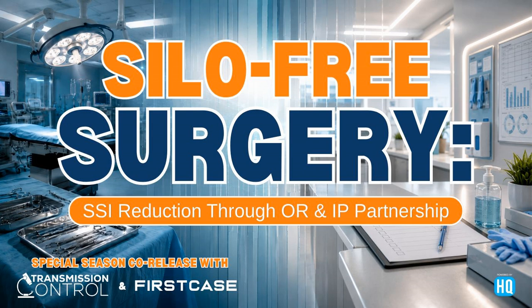Right. Yeah. Or somebody uses the instrument incorrectly in the OR and there's damage or a chip or something. Yes. But I think that's an important call out: if something's broken, your IFU is not designed to clean a broken, damaged instrument that genuinely needs to be repaired. That's correct. And from my understanding, for all the IFUs that I've seen in the last 24 years, there is a precaution page in there that says if you see this broken, or if you see this loose, or if you see discoloration in this area, return it back to the OEM, right? And do not use or discard. So manufacturers do give some guidance in that area to ensure that it doesn't get reprocessed.